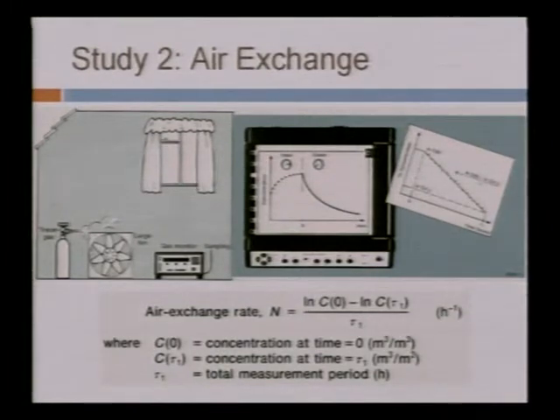And the next one is the air exchange study. And this is how it looks. Basically, we have a tracer gas, and we inject it to the room, and we operate the fans to mix it. And then we have a sensor, and the sensor will sample the gas concentration going up during the dosing period, and then we let it decay. It will decay because of the infiltration from outside air. There are fresh air coming in, then the concentration drops. And if we put this chart into a logarithmic scale, we should have a very nice decay, a straight line, where we can calculate the N, the number of air changes per hour.